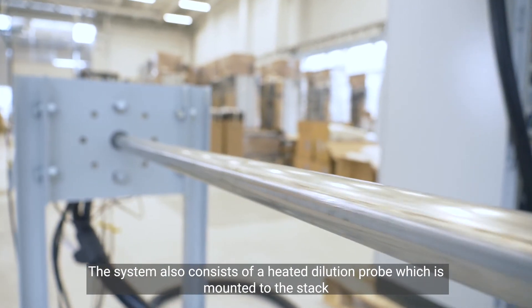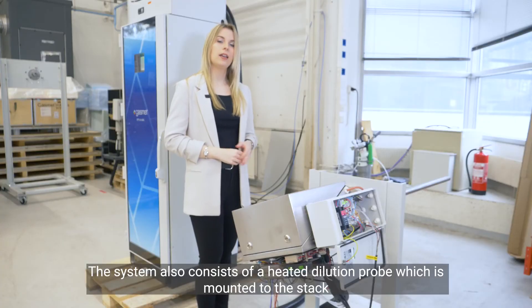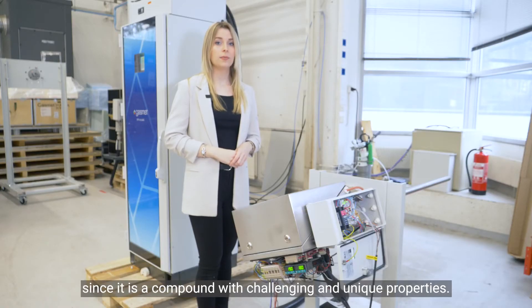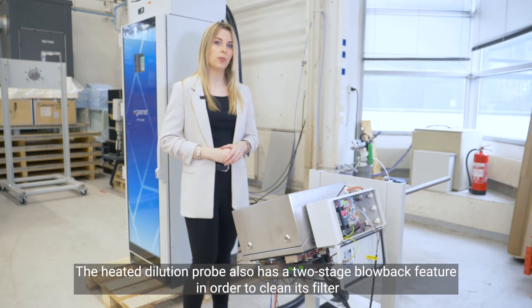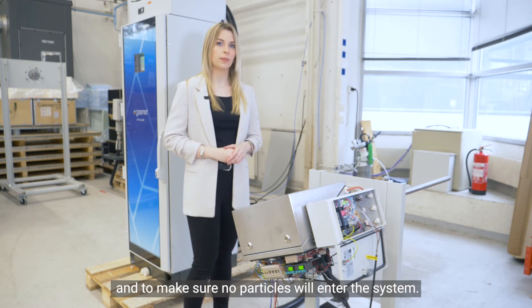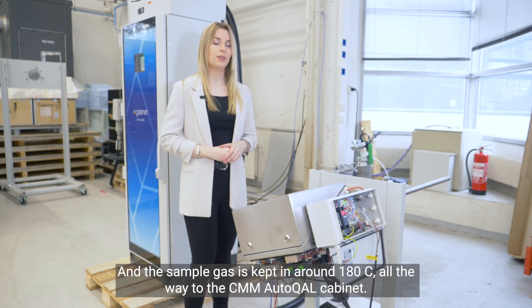The system also consists of a heated dilution probe which is mounted to the stack, and a heated sample line which is especially designed for sampling mercury, since mercury is a compound with challenging and unique properties. The heated dilution probe also has a two-stage blowback feature to clean its filter and ensure no particles will enter the system. The sample gas is kept at around 180 degrees Celsius all the way to the CMM AutoQAL cabinet.